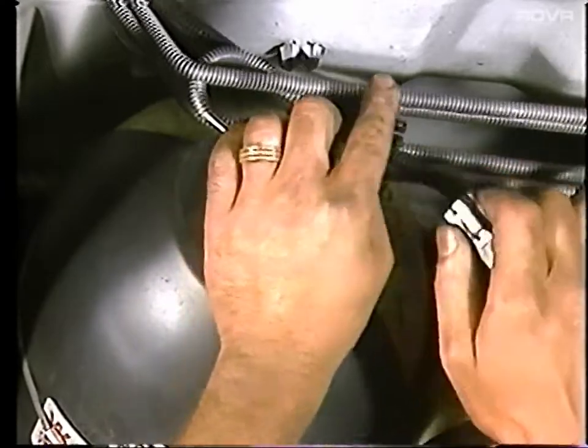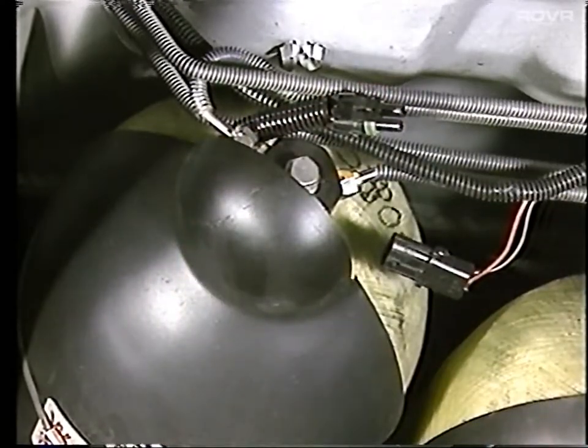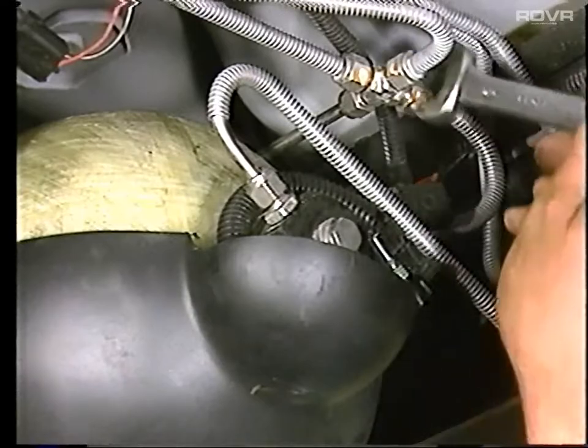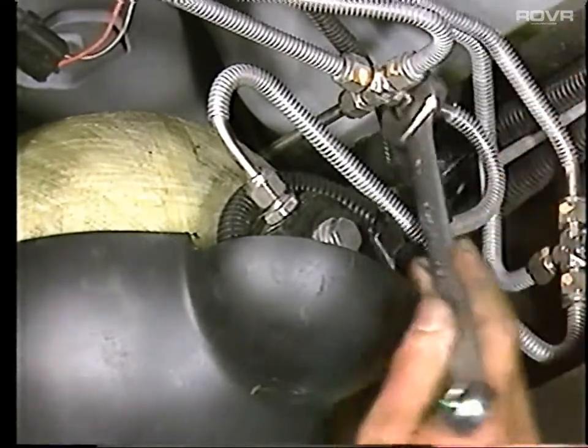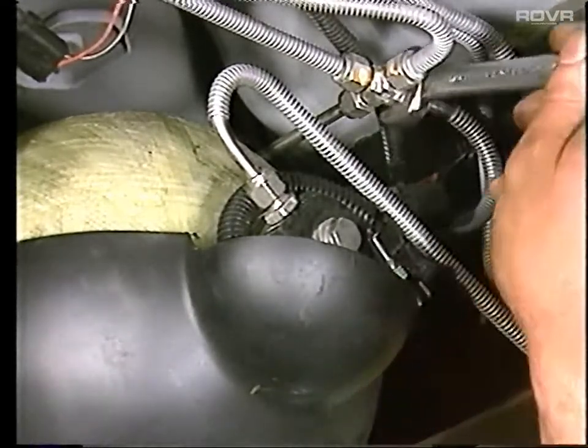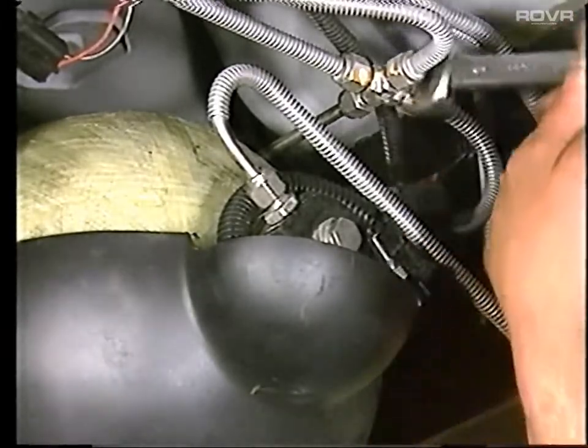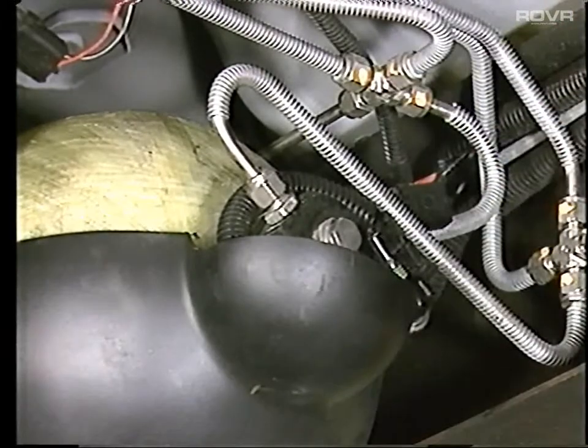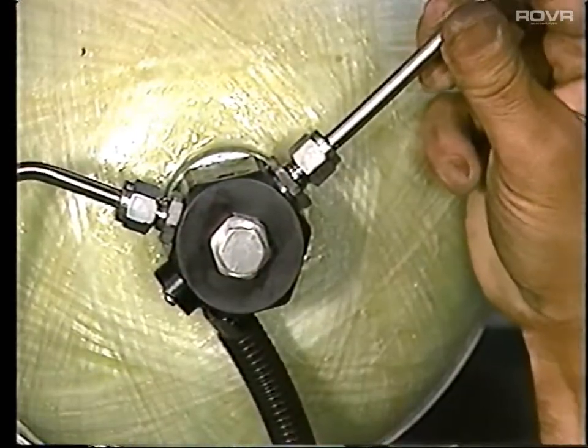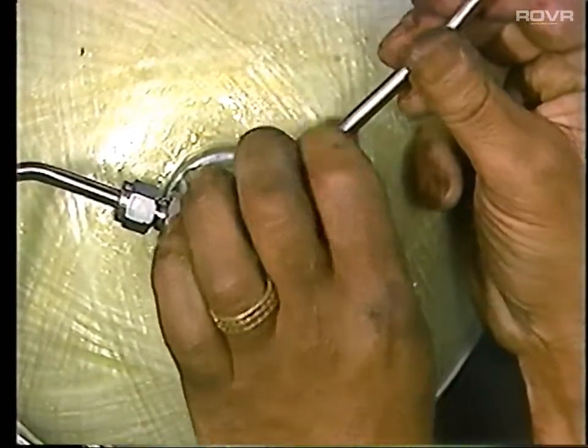Remove the tank shield from the tank. Disconnect the wiring connector serving the faulty in-tank solenoid valve. Now, you'll have to vent the tank. First, go to the four-way T connector and quickly loosen the fitting of the shortest line until the flow stops. This will allow the fuel to quickly escape, causing the excess flow valve to close, stopping the release of gas from the tank. Second, remove the supply tube serving the fill side of the valve.